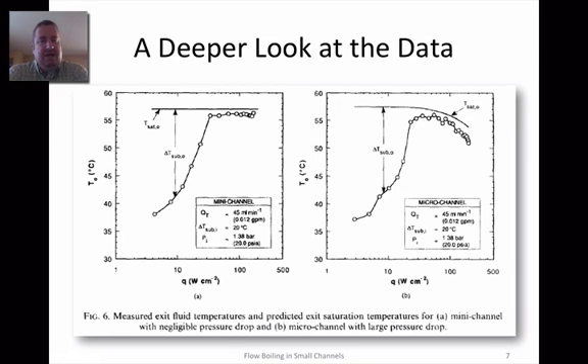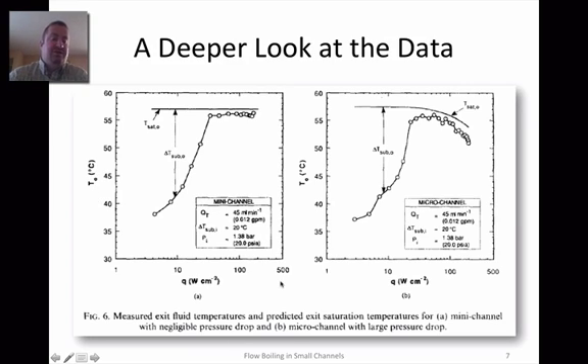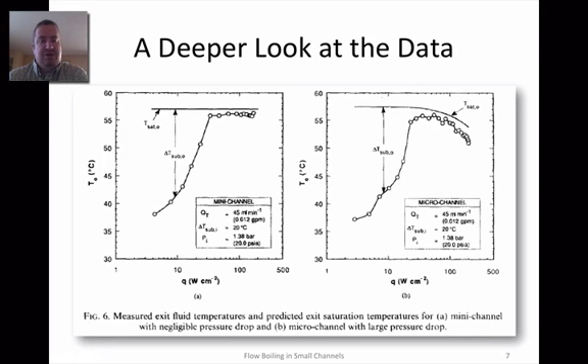One of those differences is a big pressure drop in the micro channel as compared to the mini channel, which had a very small pressure drop. Here he's digging into the data a bit deeper. In this case you have the outlet temperature as a function of heat flux. As heat flux increases you expect the outlet temperature to increase, of course. But once you start to boil, you have a two-phase mixture with latent heat, and you reach a plateau in outlet temperature a little bit under the saturation temperature of the outlet condition. That's because you have a two-phase mixture, and once it comes out, some condensation will occur because you've lost your heat source.